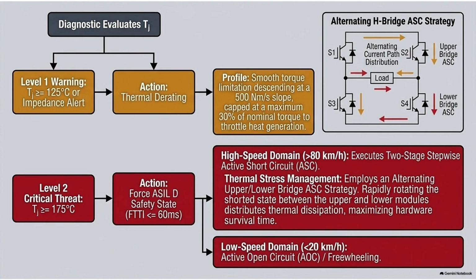It knows immediately that it's a short circuit. So it doesn't even need the software code. No. If the signal steps outside that 0.5 to 4.5 volt boundary for even a fraction of a millisecond, the physical hardware comparator trips an alarm and shuts the system down. It is a hardwired reflex.